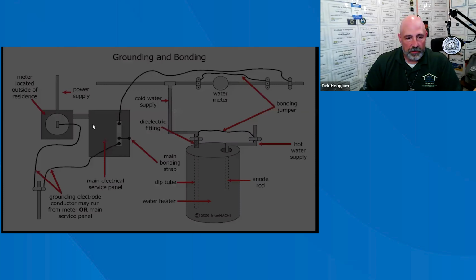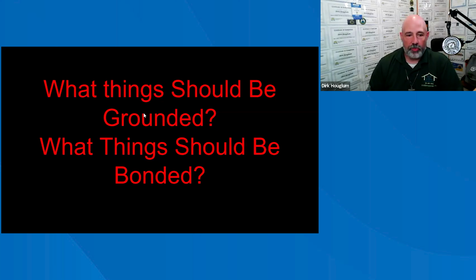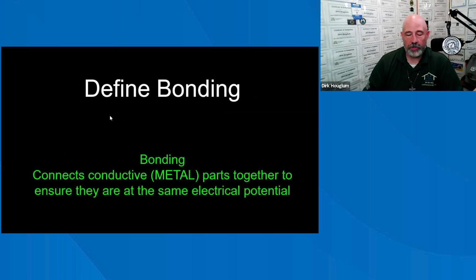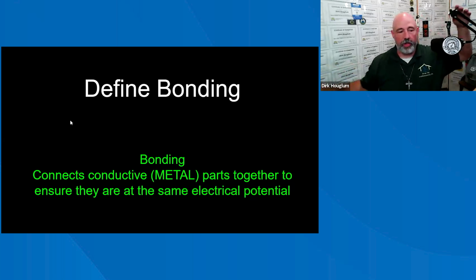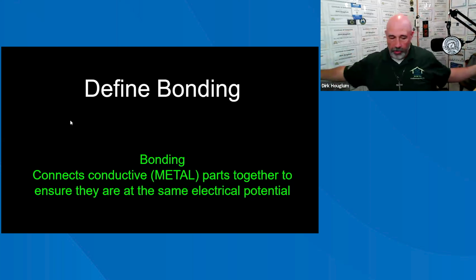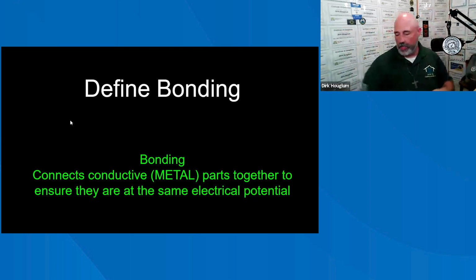All right, onward to this. What things should be grounded? What things should be bonded? Just like Robert just asked about the CSST, that definitely needs to be bonded, of course. So let's define bonding. Bonding connects metal parts together so they ensure the same electrical potential. Like I said, if I took an ohms meter and I have this bonded with the microphone, there's a wire in between. I should be able to put it anywhere on any of this system and it should have the same potential. It should be at 0 ohms.